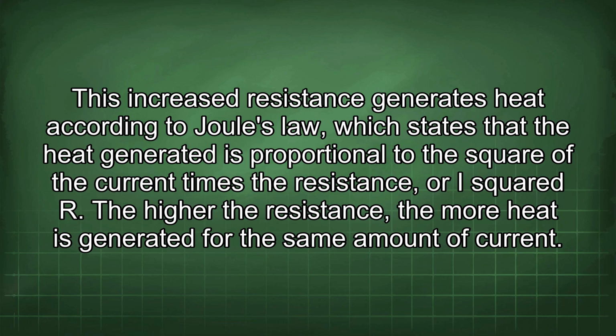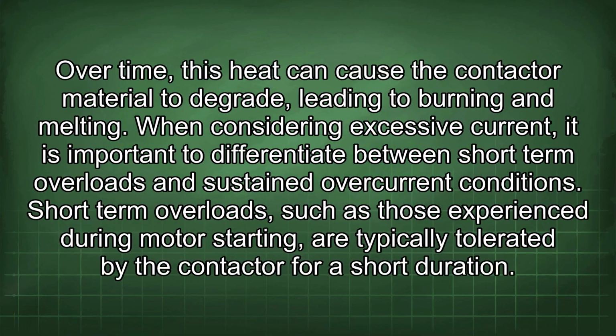The higher the resistance, the more heat is generated for the same amount of current. Over time, this heat can cause the contactor material to degrade, leading to burning and melting. When considering excessive current, it is important to differentiate between short-term overloads and sustained overcurrent conditions. Short-term overloads, such as those experienced during motor starting, are typically tolerated by the contactor for a short duration.